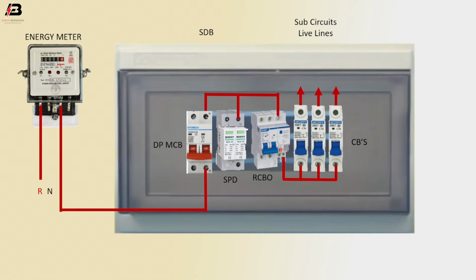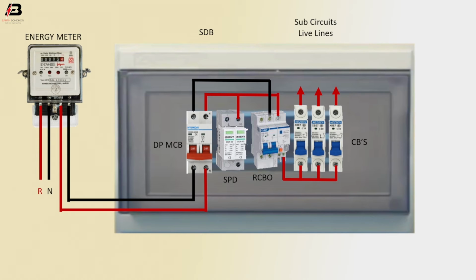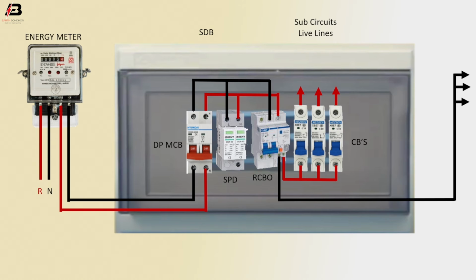Live line, neutral connection connected to energy meter, neutral connection from energy meter to connect double pole MCB, neutral connection from double pole MCB to connect RCBO circuit breaker and SPD, neutral connection from RCBO circuit breaker for load.